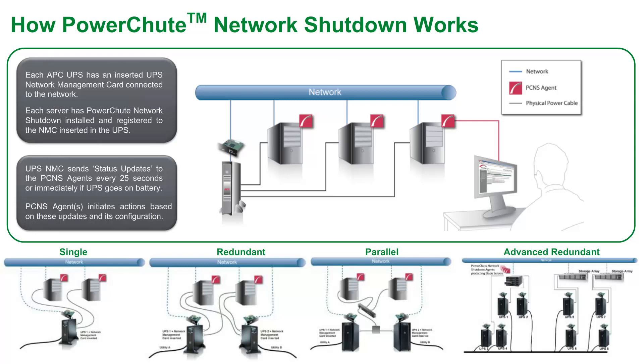The UPS Network Management Card sends status updates every 25 seconds to each PowerChute agent, or immediately if there is a state change, such as the UPS switching to battery power. PowerChute will then initiate actions such as running a command file or starting a shutdown sequence, depending on the nature of the UPS events and how PowerChute is configured.